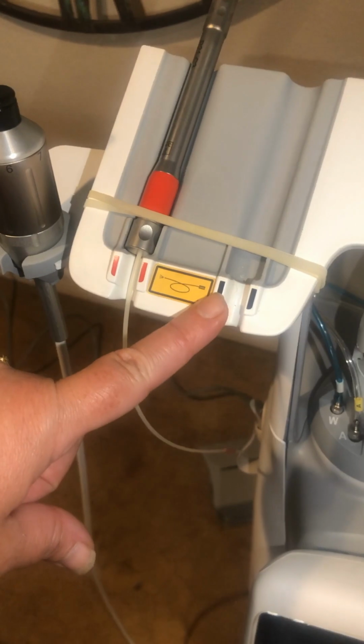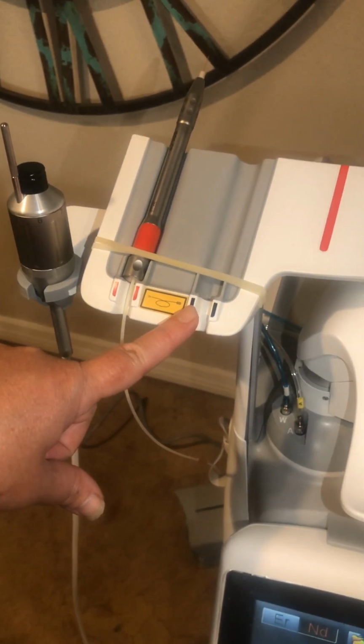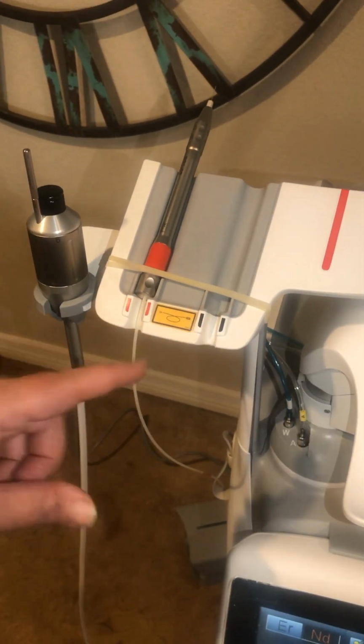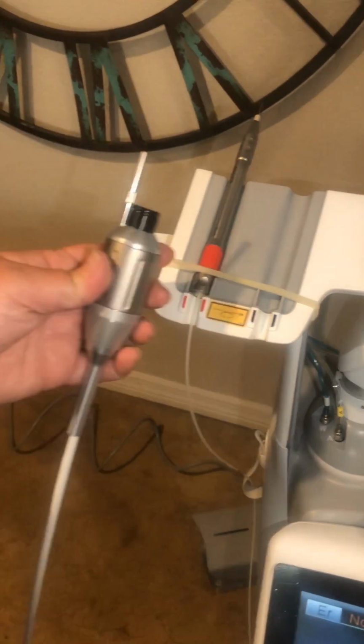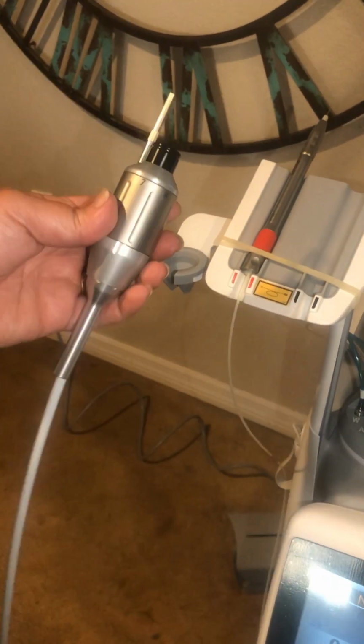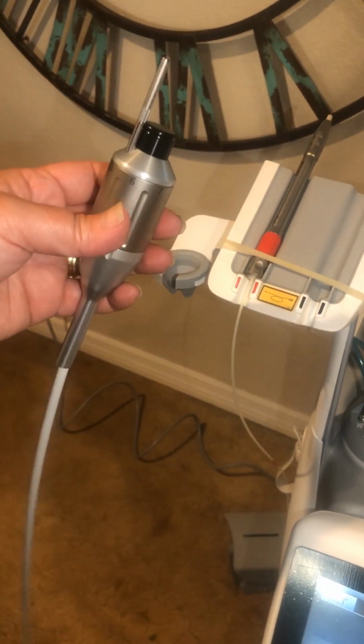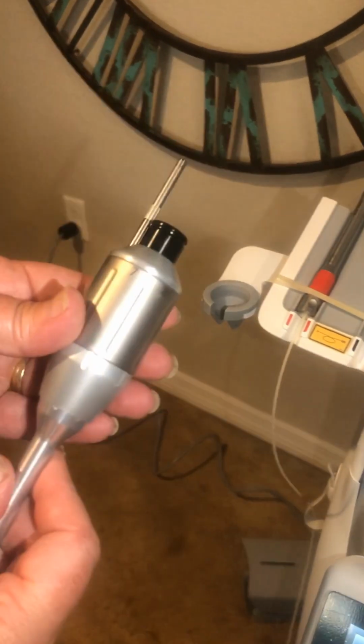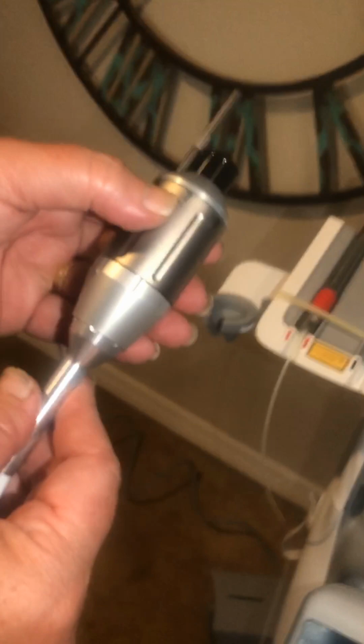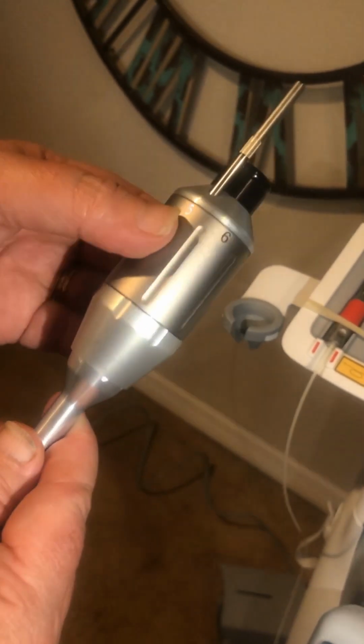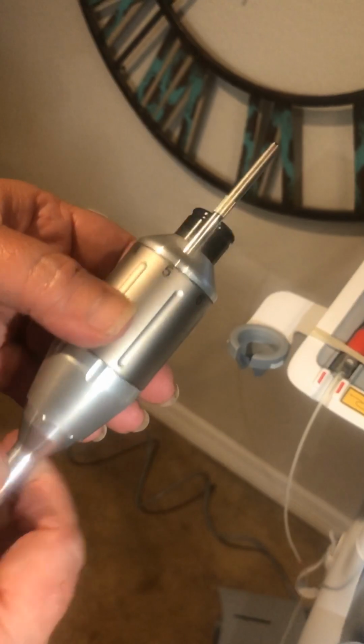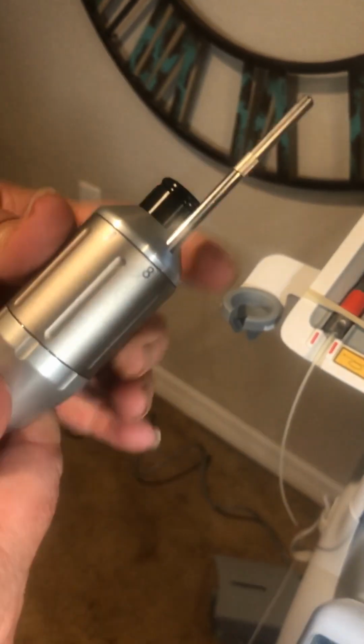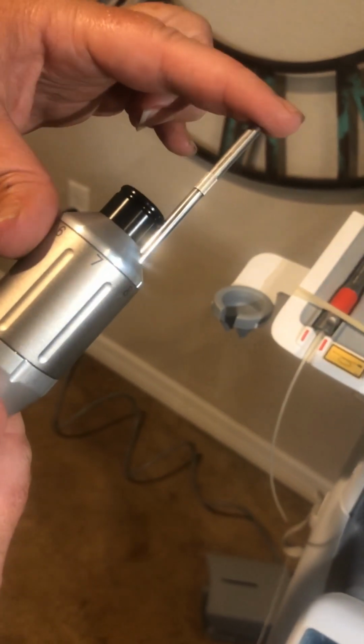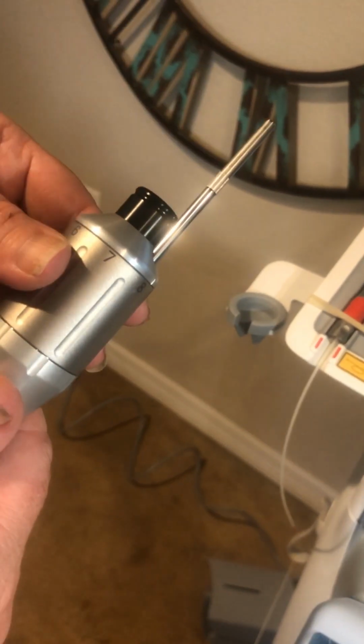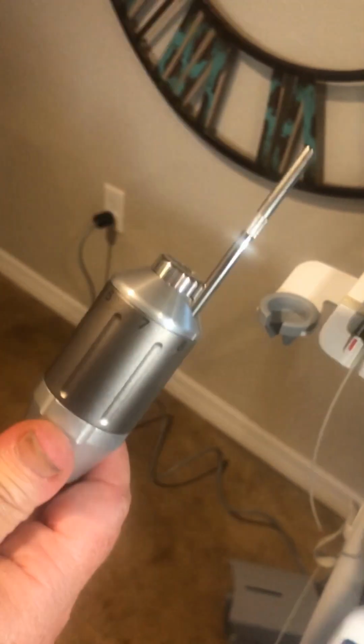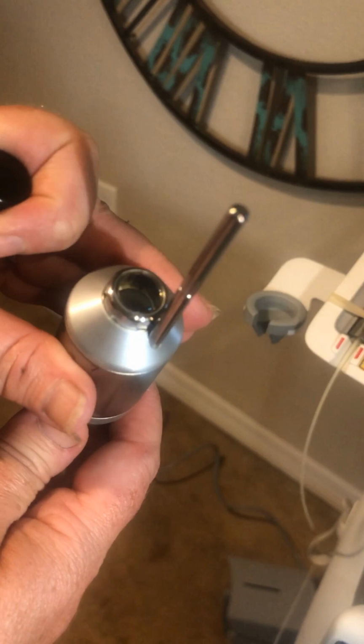Those are the chromophores that the ND YAG is targeting, blood and pigment. And so let's start with the R30A handpiece. This is your aesthetic and dermatologic handpiece. It is going to create a larger spot size. There's a dial on here. You'll see lots of numbers along the edge, and those line up with this wand. And as I turn the dial, that wand extends and gives a greater distance from the target, which gives a greater spot size. This lens cap pulls straight off, and then that exposes the lens of the R30A.